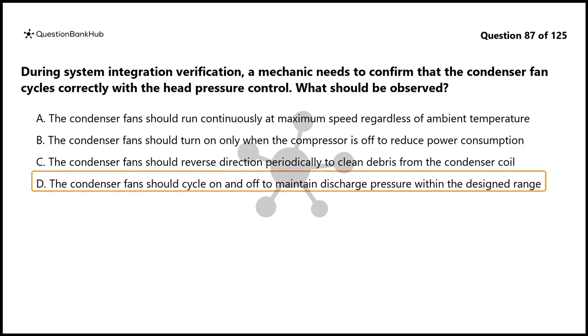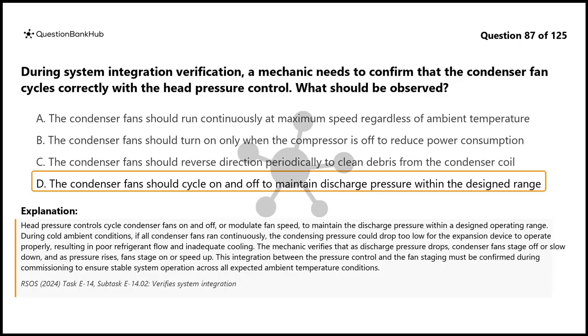The correct answer is D. Head pressure controls cycle condenser fans on and off, or modulate fan speed, to maintain the discharge pressure within a designed operating range. During cold ambient conditions, if all condenser fans ran continuously, the condensing pressure could drop too low for the expansion device to operate properly, resulting in poor refrigerant flow and inadequate cooling.